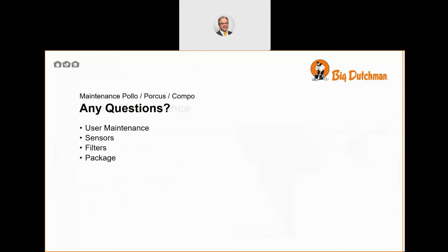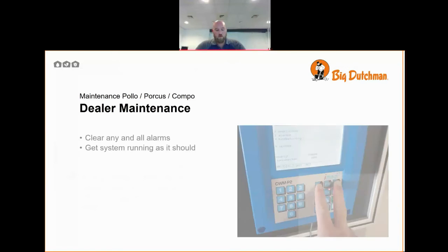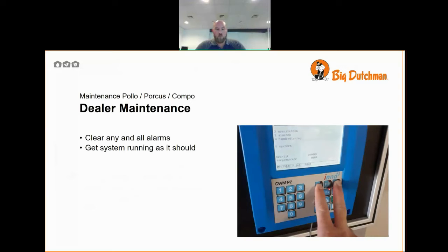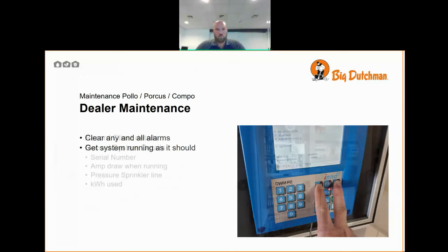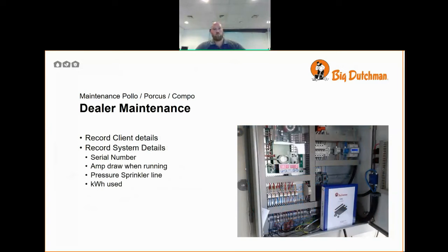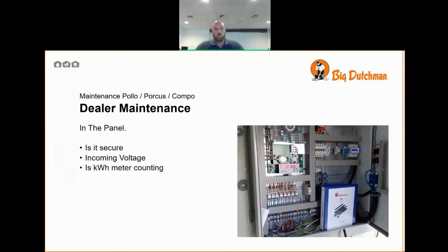Moving on to dealer or technician maintenance. The first thing that we're going to want to do is to solve and clear any alarms and get the system running as it should. Record the client's details and record the system details. So the serial number, the amperage draw across the pump while it's running, the pressure on the sprinkler line, the kilowatt hours used. All these details are also available in a servicing form that we have available to you.